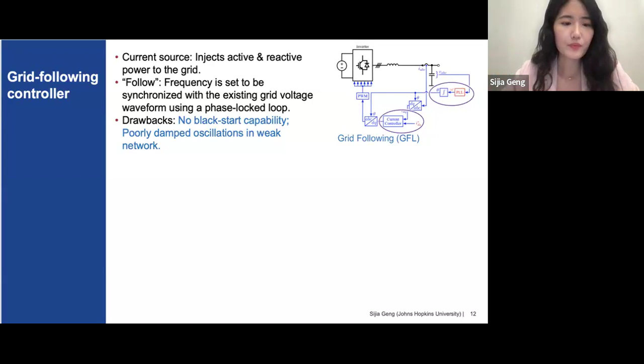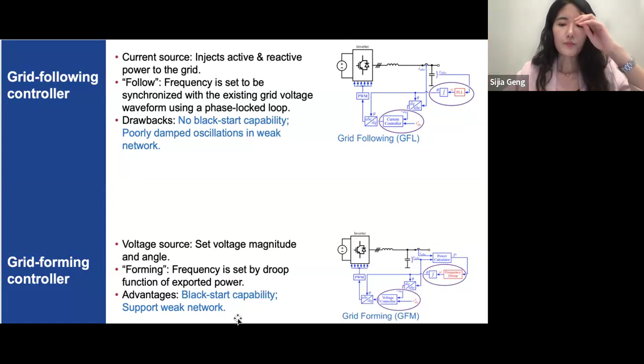On the other end of the spectrum, we have grid-forming inverters, which form a certain desired voltage at their terminal. The synchronization to the grid in this specific implementation is through the frequency droop characteristic. The grid-forming inverter should be able to achieve black start and provide a range of grid services. Now, in between these two ends of the spectrum, there are numerous possible implementations, and I only showed some possibilities here. So in the future, we need to make sure all these different controllers interact with each other properly, and we need a systematic tool to study this problem.